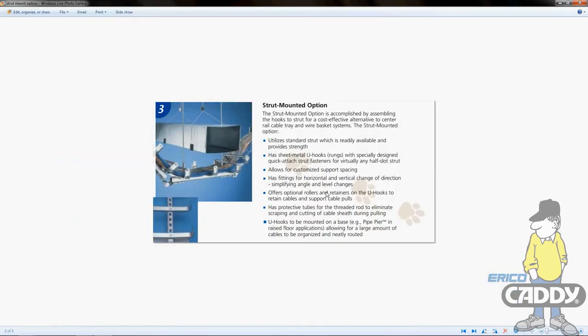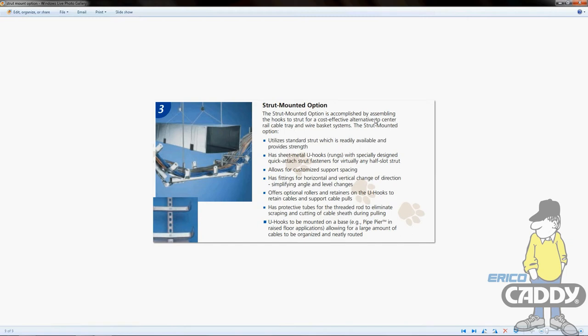Now the strut mounted option is the third option out of three - the first one would be the rod, the second the cantilever. If you're going to go this route, you'll order the U-hooks with the T-nut. If you're going the other route, you probably want to order them without the T-nut. This option is a great alternative and cost-effective alternative to center rail cable tray and wire basket systems.